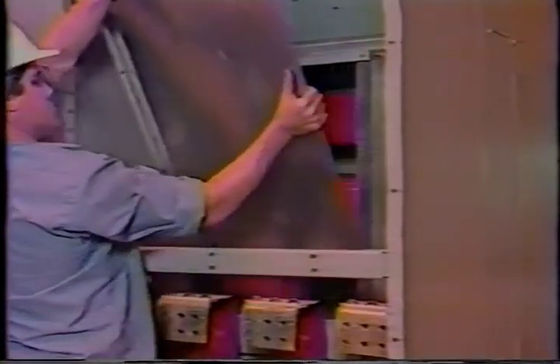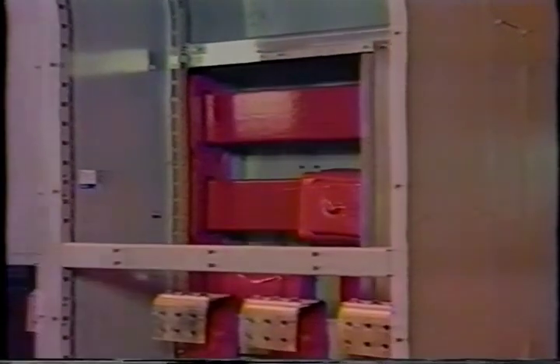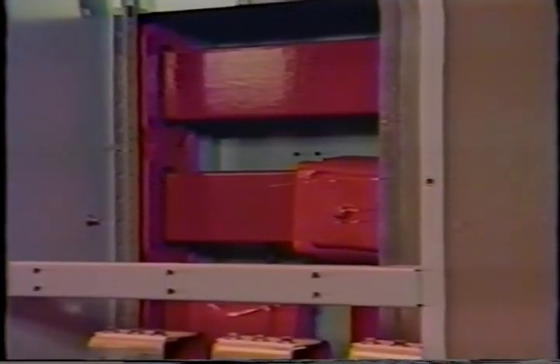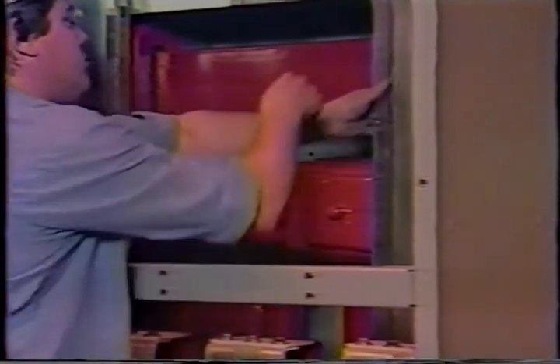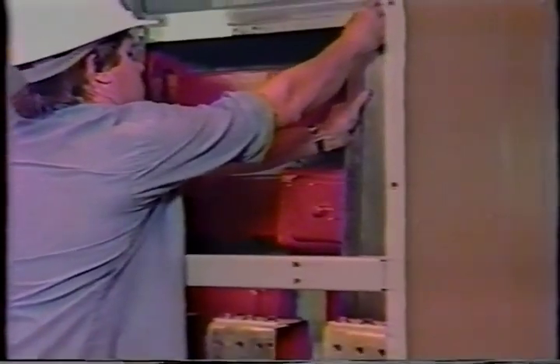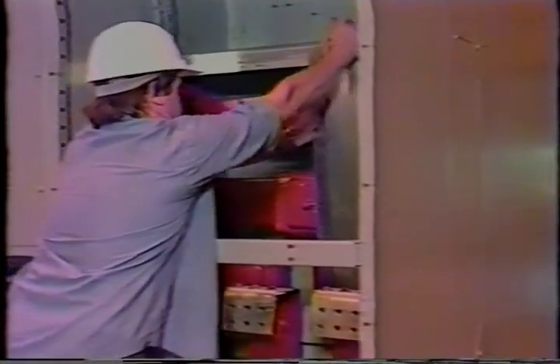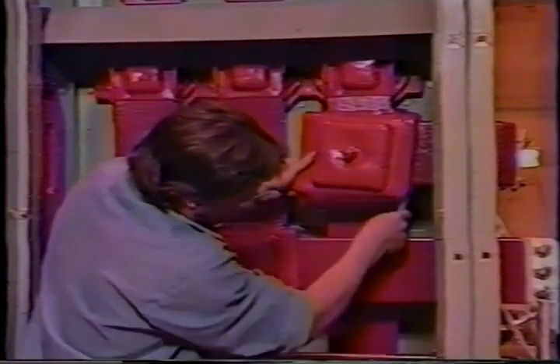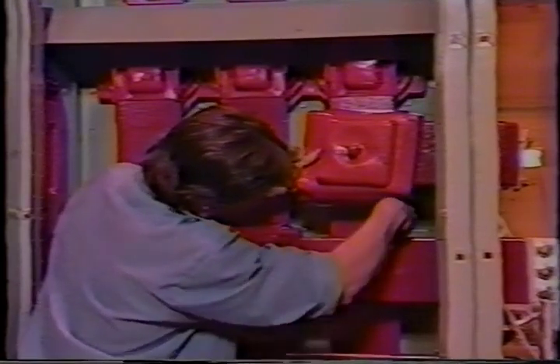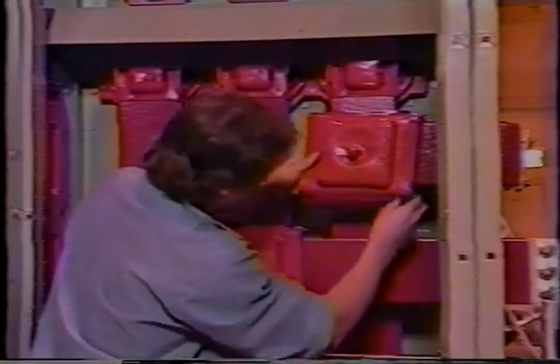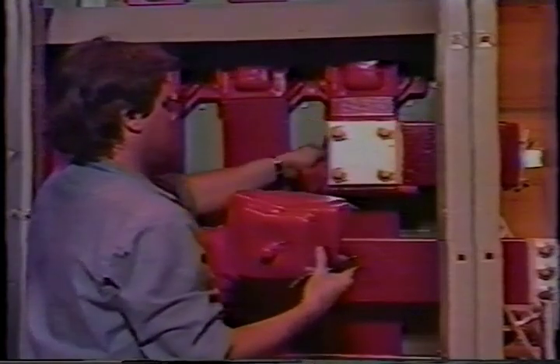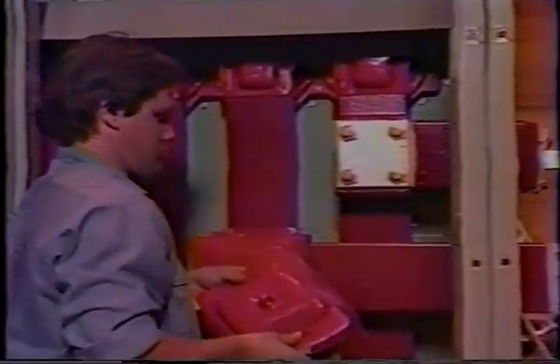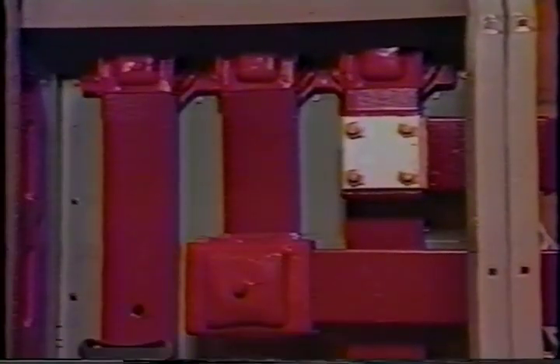The horizontal and vertical metal barriers must be removed from the cable compartment as well as the main bus barrier. Other obstructions may also have to be dismantled. Splice plates, boots, and hardware are furnished to bridge the shipping splits. These are already secured to the risers at each shipping split.